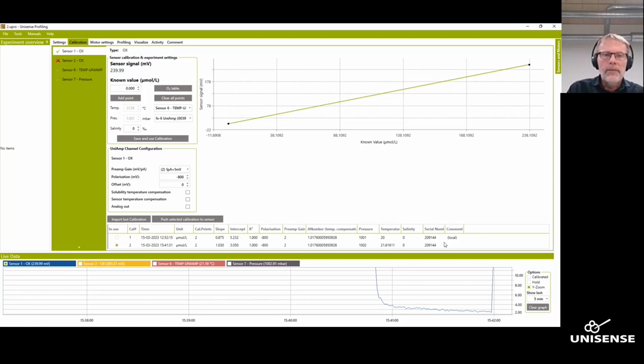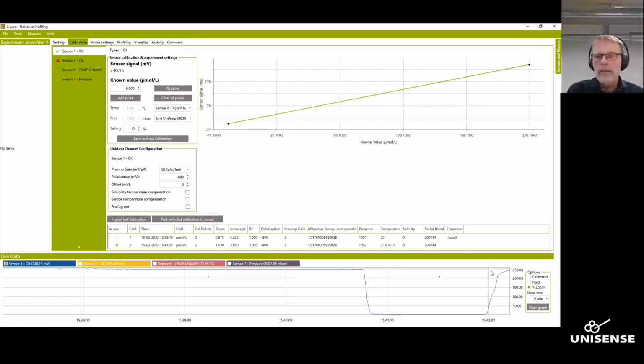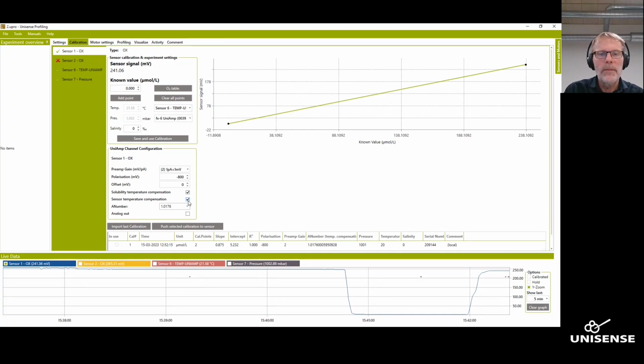Yeah. So now the signal has jumped back up again. So I want to use the temperature compensation. There are these two, as I mentioned yesterday, the solubility temperature compensation and the sensor temperature compensation.